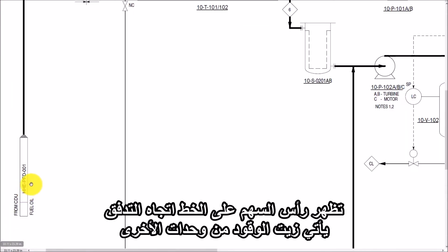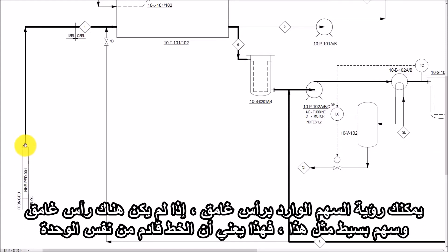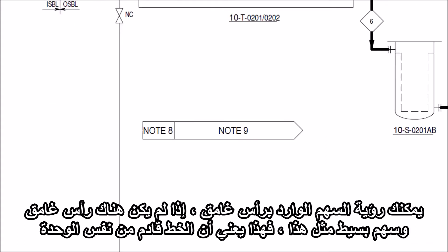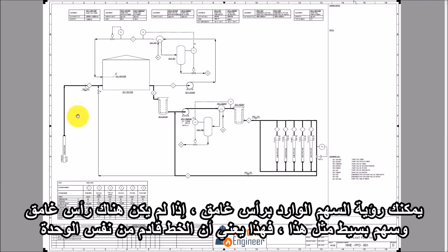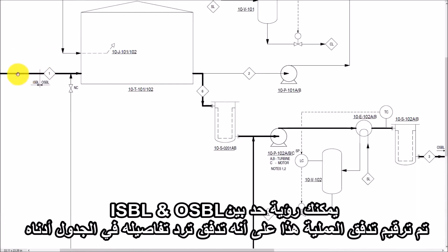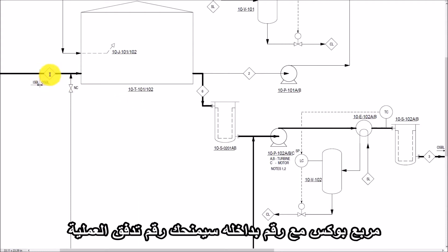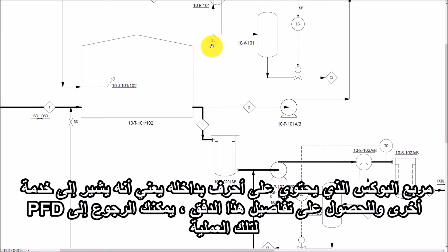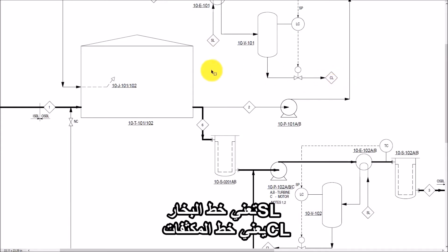Fuel oil is coming from the other ISBL unit. You can see the incoming arrow with the dark head. If there is no dark head and a simple arrow is there, it means the line is coming from the same unit. You can see the battery limit between OSBL and ISBL. This process stream is numbered as 1, for which detail is given in the table below. A square box with a number inside gives you the process stream number. A square box with a letter inside means it refers to another service, and for the detail of that stream you have to refer to the PFD of that process. Here, SL means Steam Line and CL means Condensate Line.